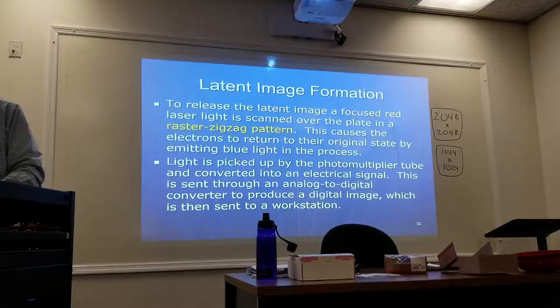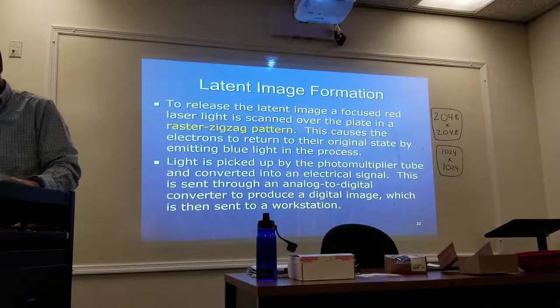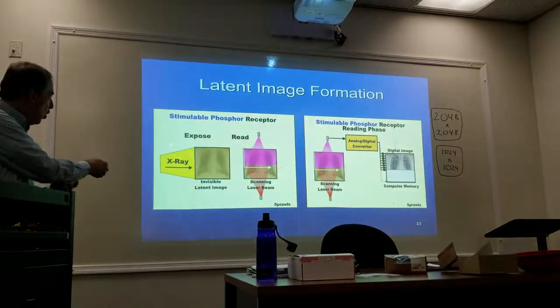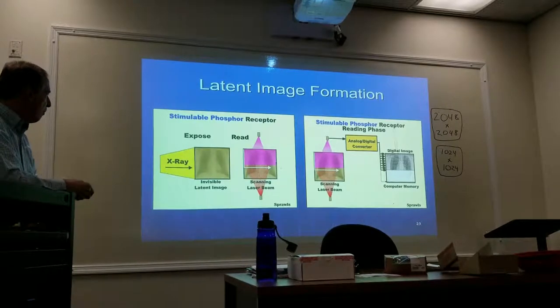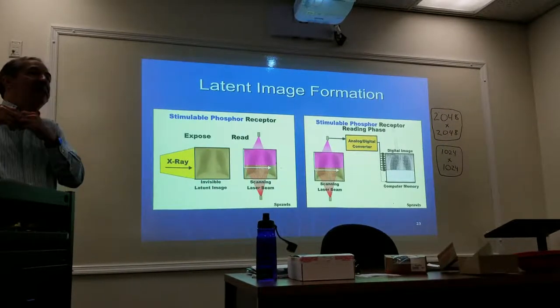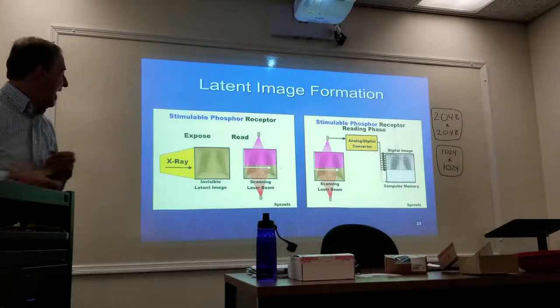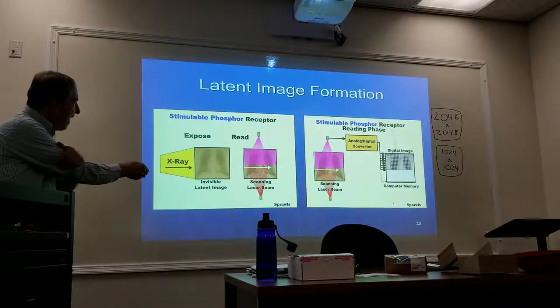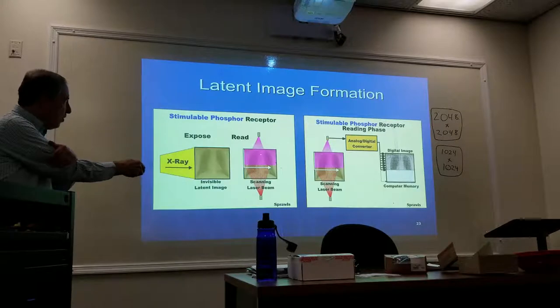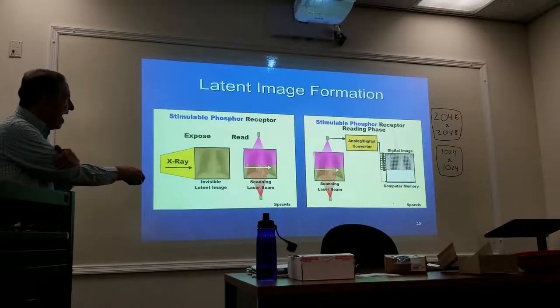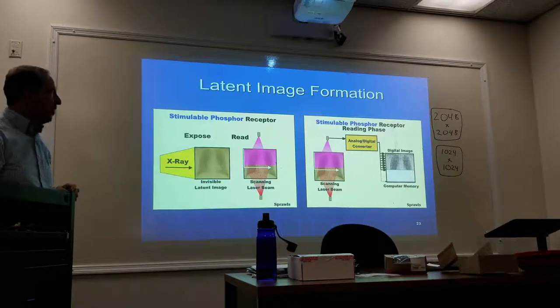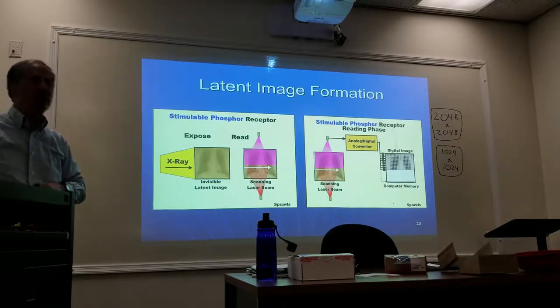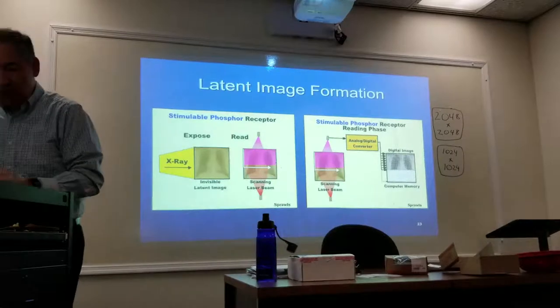This causes the electrons, because they're in that metastable state, to come back to their original state by emitting light — that's the signal. The light is picked up by the photomultiplier tube and converted into an electrical signal. So: x-rays strike the photostimulable plate, creating a latent image; the red light goes in that raster zigzag pattern, the image appears, it goes through the analog-to-digital converter, and now you have your visual image.